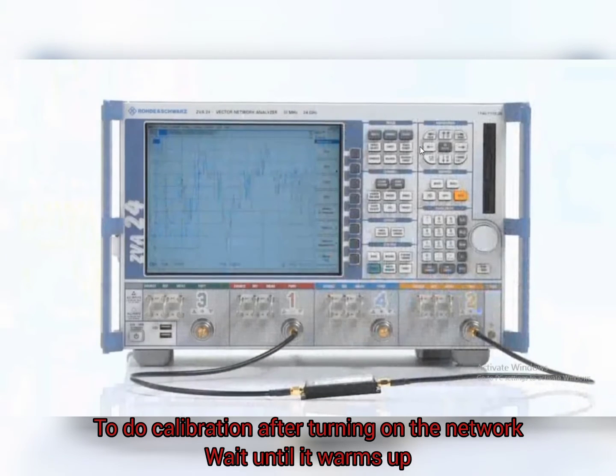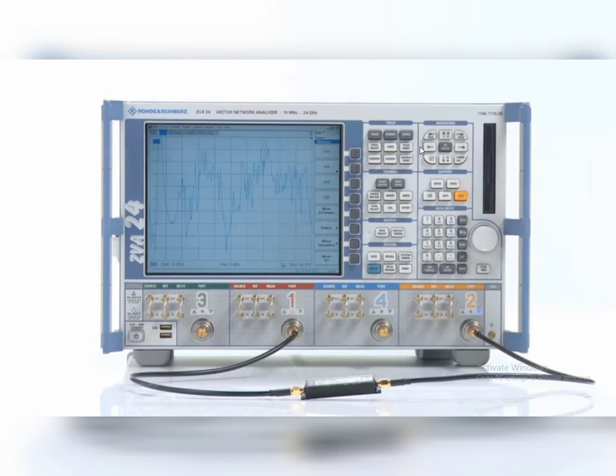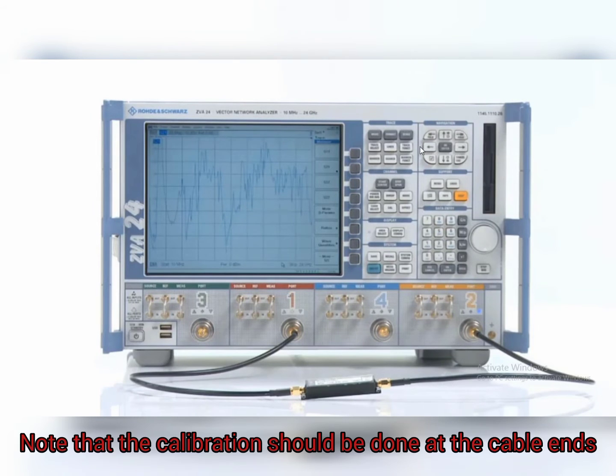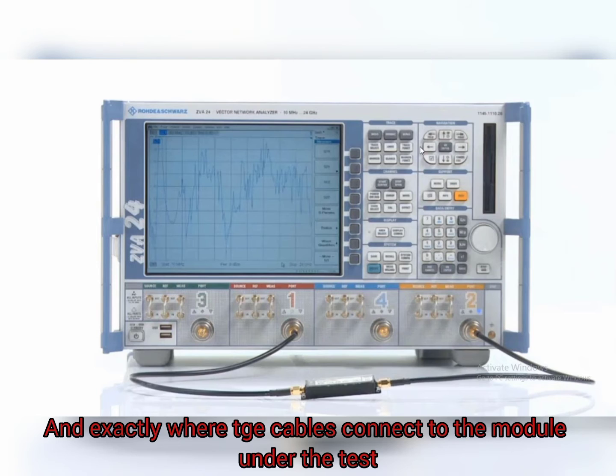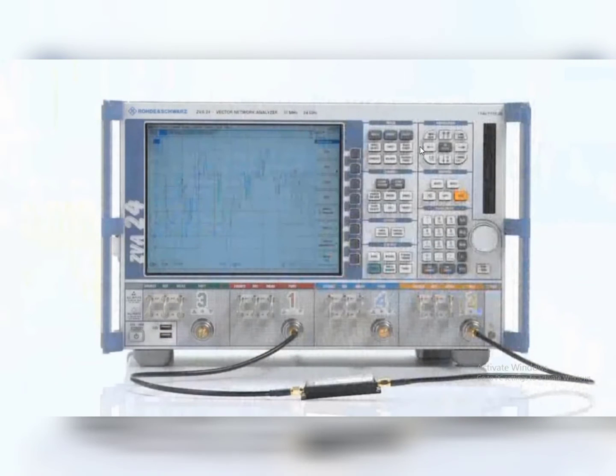To do calibration after turning on the network analyzer, wait until it warms up. Note that the calibration should be done at the cable's end and exactly where the cables connect to the module under test.